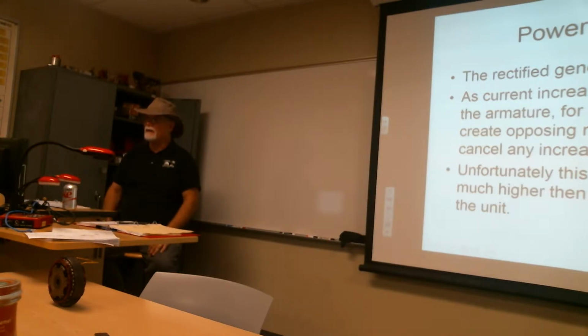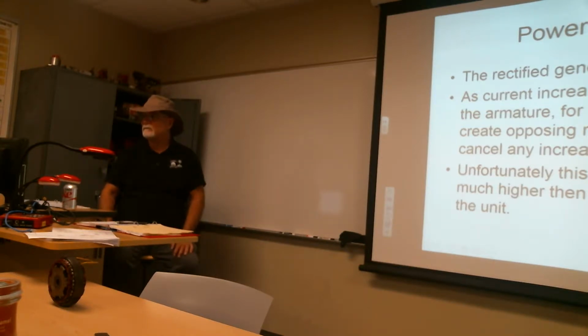So in that particular case, let's say I rated it at 50 amps - its true self-limiting output might be 170 amps, but its cooling capacity was only 55 or 60 amps. So now you throw a wrench across it, it goes direct to 170 or 180 amps, whatever that is. This one can't do that. It just can't do it.